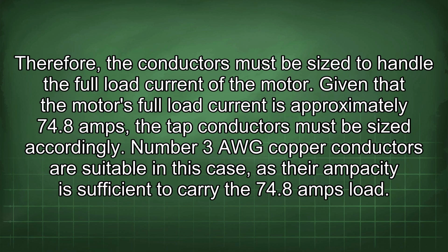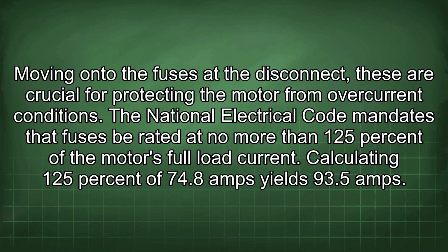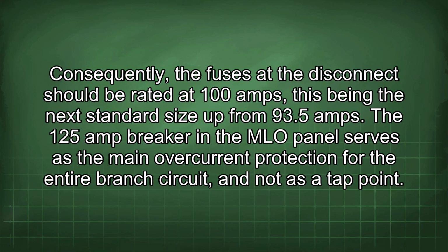Given that the motor's full load current is approximately 74.8 amps, the tap conductors must be sized accordingly. Number 3 AWG copper conductors are suitable in this case, as their ampacity is sufficient to carry the 74.8 amp load. Moving on to the fuses at the disconnect, these are crucial for protecting the motor from overcurrent conditions. The National Electrical Code mandates that fuses be rated at no more than 125% of the motor's full load current. Calculating 125% of 74.8 amps yields 93.5 amps. Consequently, the fuses at the disconnect should be rated at 100 amps, this being the next standard size up from 93.5 amps.